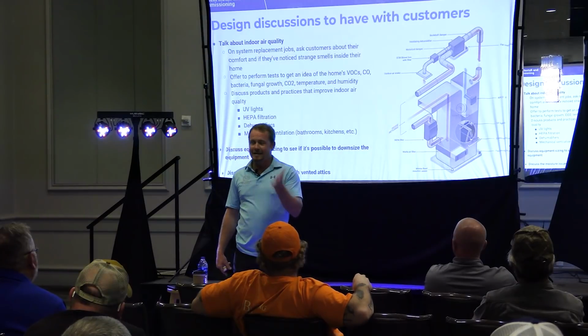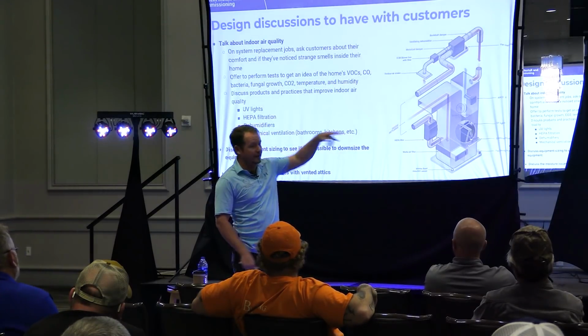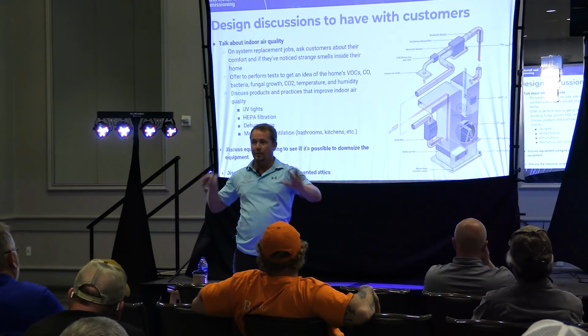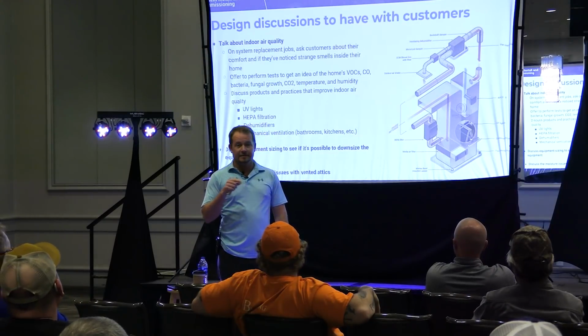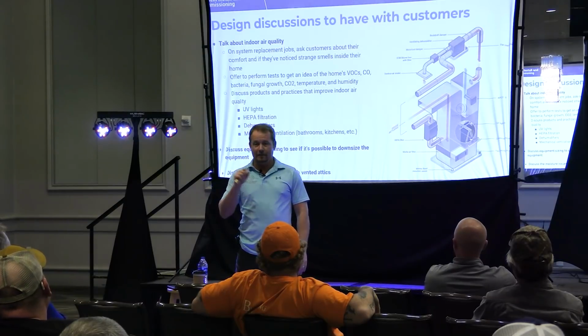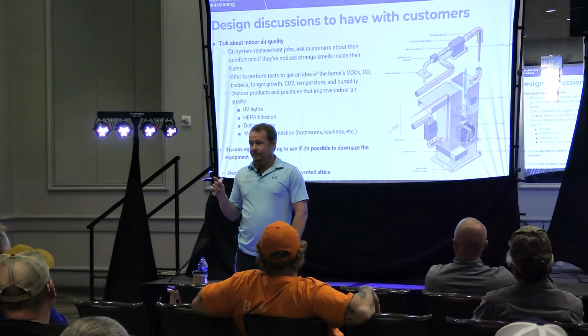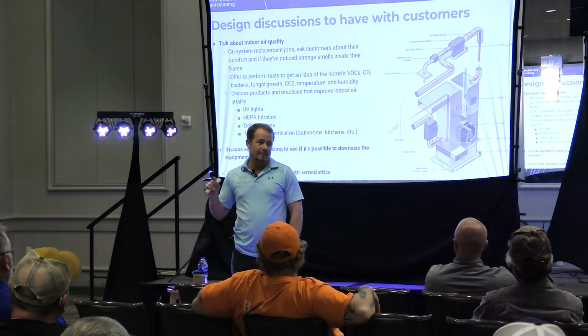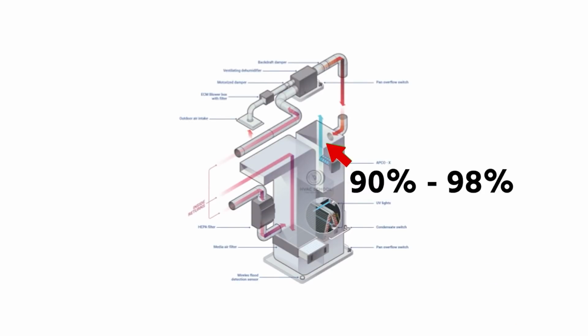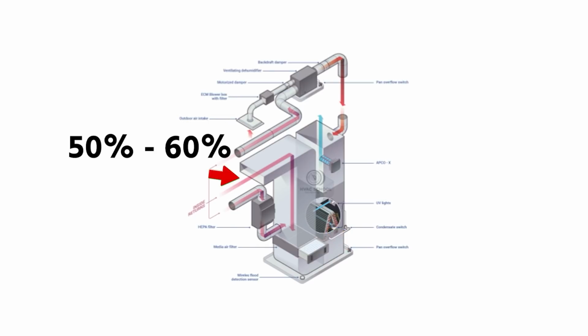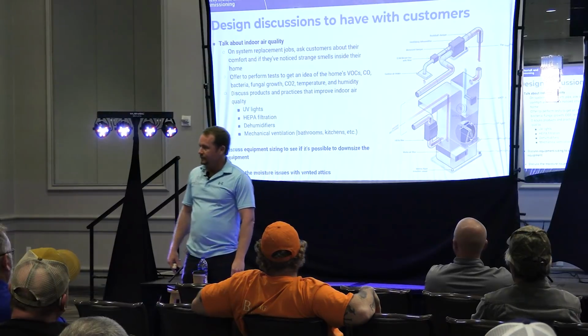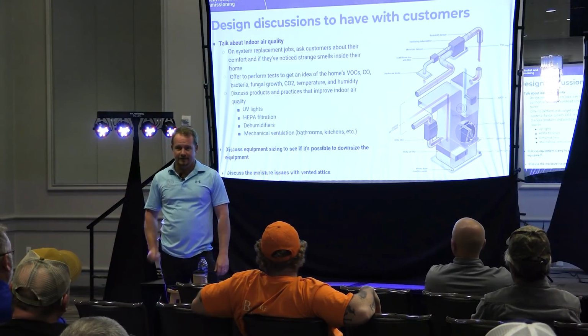Now here's a tricky thing: has anybody ever measured the relative humidity in the supply duct? I want to be clear about what we mean when we say dry - it's actually very high relative humidity. If you've never done it, do it sometime, it's going to measure somewhere between 90 and 98% generally. How on earth could the air in the supply duct be 90 to 98% relative humidity when it just went over the evaporator coil, you saw the water come out and drain out the drain, and in the return it was 50%, 55%, or 60%, hopefully less than that? Because it's relative - relative to temperature, right?